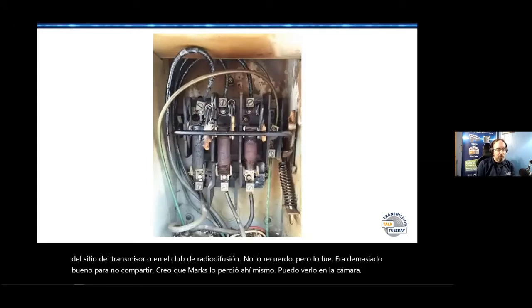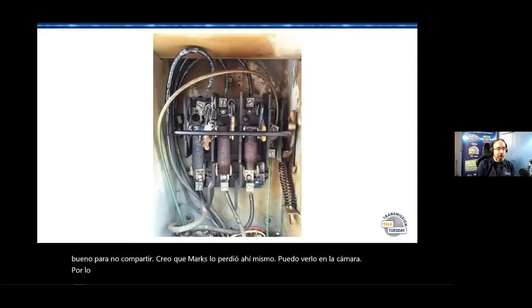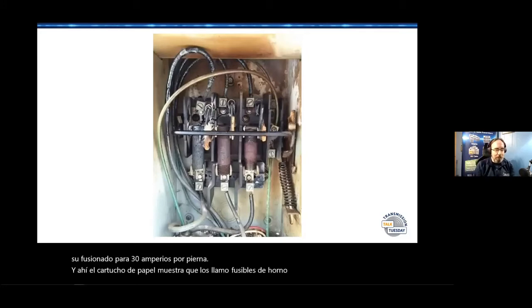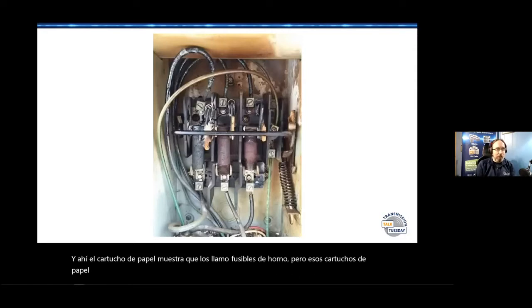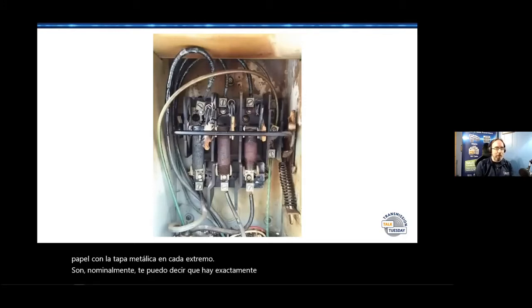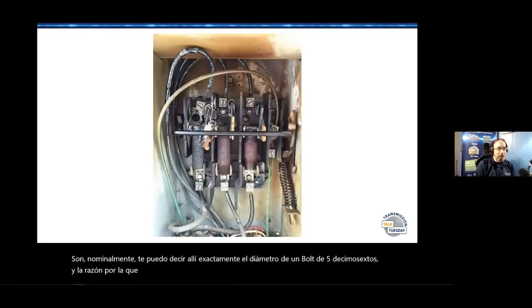For what it's worth, in the surge protectors we used to make, they're fused for 30 amps per leg. And the paper cartridge fuses, what I call oven fuses, with the metal cap on each end, are nominally exactly the diameter of a 5/16 bolt. The reason I know this is we got one back that had literally exploded after somebody replaced all three fuses with 5/16 inch bolts.